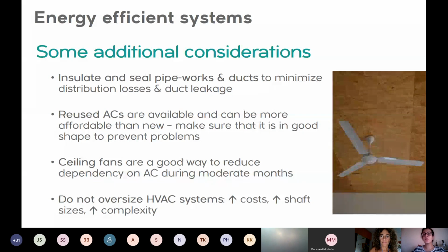And finally, it's important not to oversize HVAC systems. The bigger is not always the better. On the contrary, when we are oversizing, we are increasing the cost. We are increasing shaft sizes or spaces needed in the false ceiling for ducts and pipes, and we are also increasing the complexity of the system.